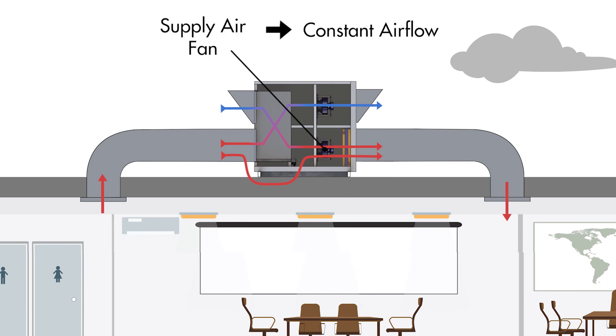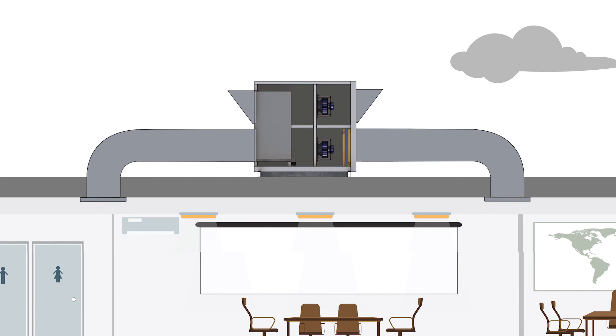The supply air fan, on the other hand, always supplies the same air flow — it's just that the outside air proportion changes. The one exception to the exhaust air fan balancing is with packaged DX units with heat or energy recovery. These require condenser make up air, and so the exhaust air volume generally needs to remain constant. But we'll cover this in a future video.